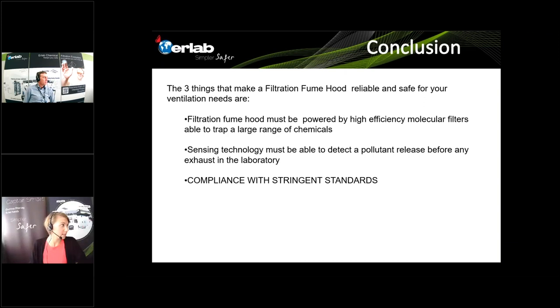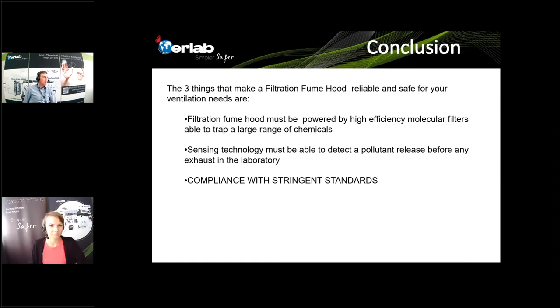How frequently is this validation or check of the fume hood recommended? The minimum is once a year, which is what we recommend according to the regulations in France. However, if your risk assessment shows you will saturate the filters earlier than one year, you can do it more frequently. Conversely, if you have a very long filter lifetime, maybe every two years is feasible.